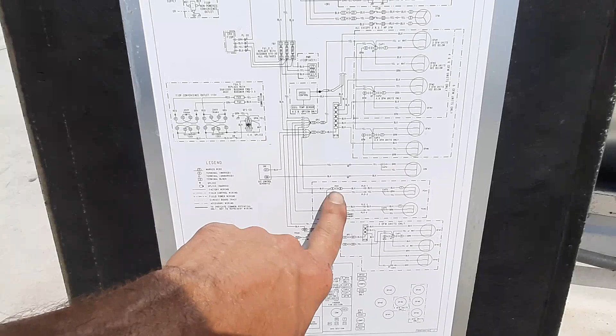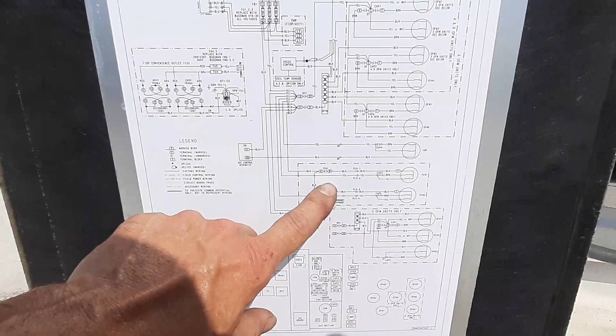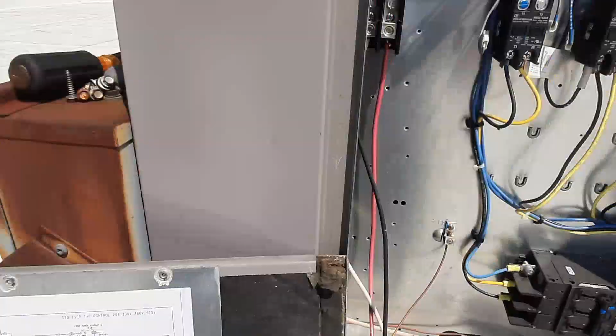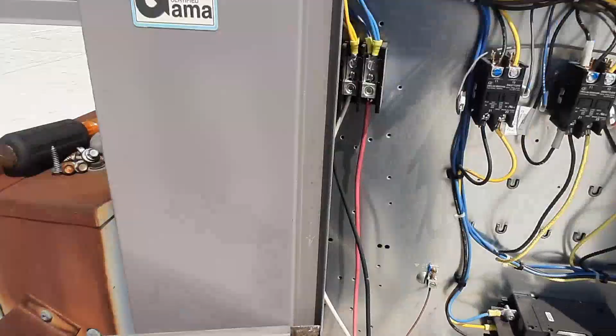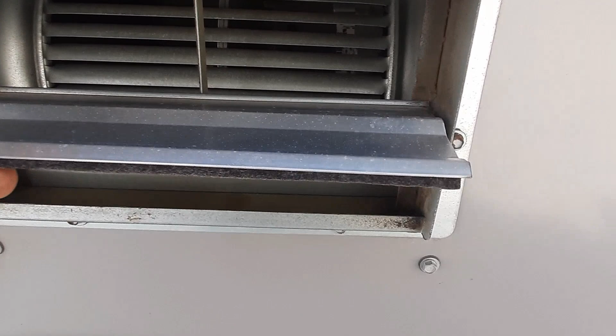As I was starting to isolate and figure out what was going on, back to my diagram, I didn't know what PER was. That is the power exhaust relay, and it feeds power exhaust motors from here. I'm still not reading a direct short, but I do have power exhaust motors. And I'll bet if I get in there to them, I find a problem.